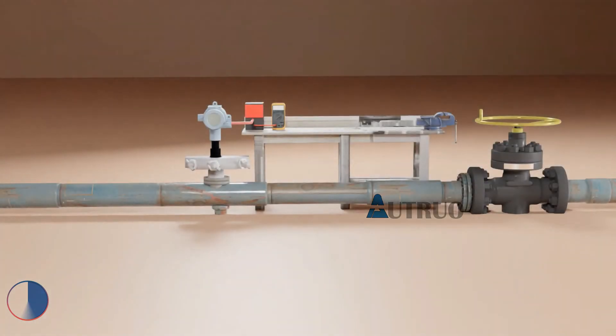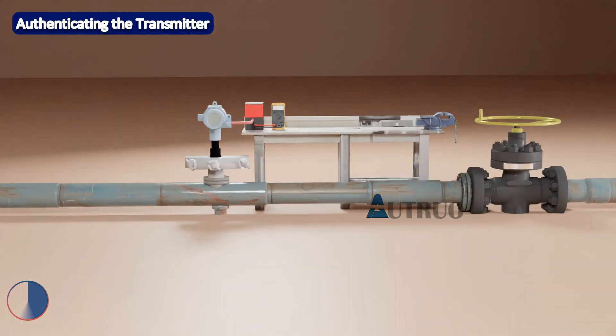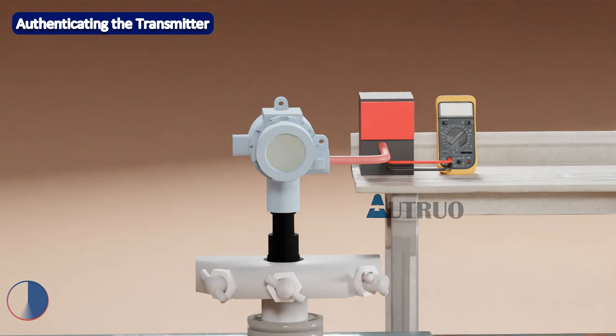We will mount the transmitter on the process pipe. Now let's authenticate the calibrated transmitter. All the valves will be at closed conditions. We will now open the equalizing valves. We will also slowly open the high pressure valves, after which we will close the equalizing valves and open the low pressure valves.